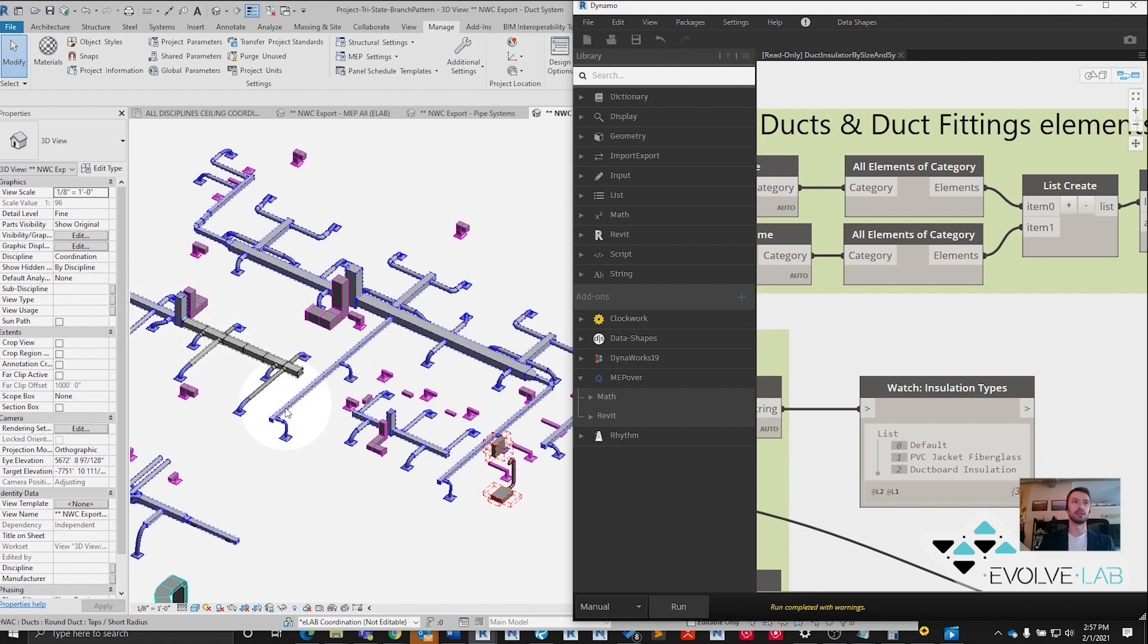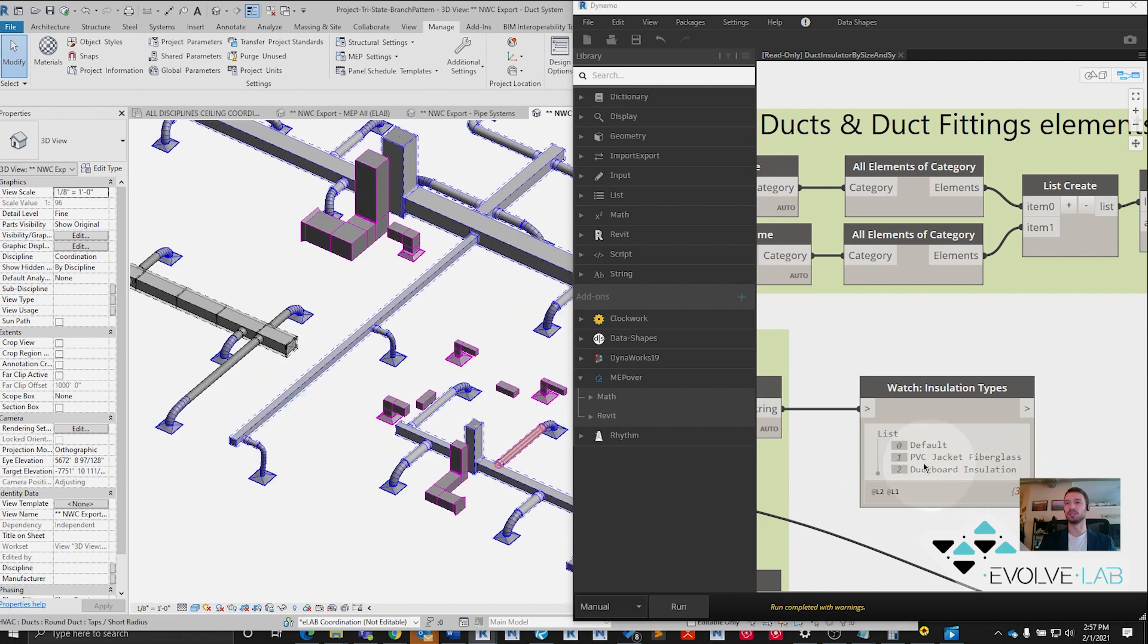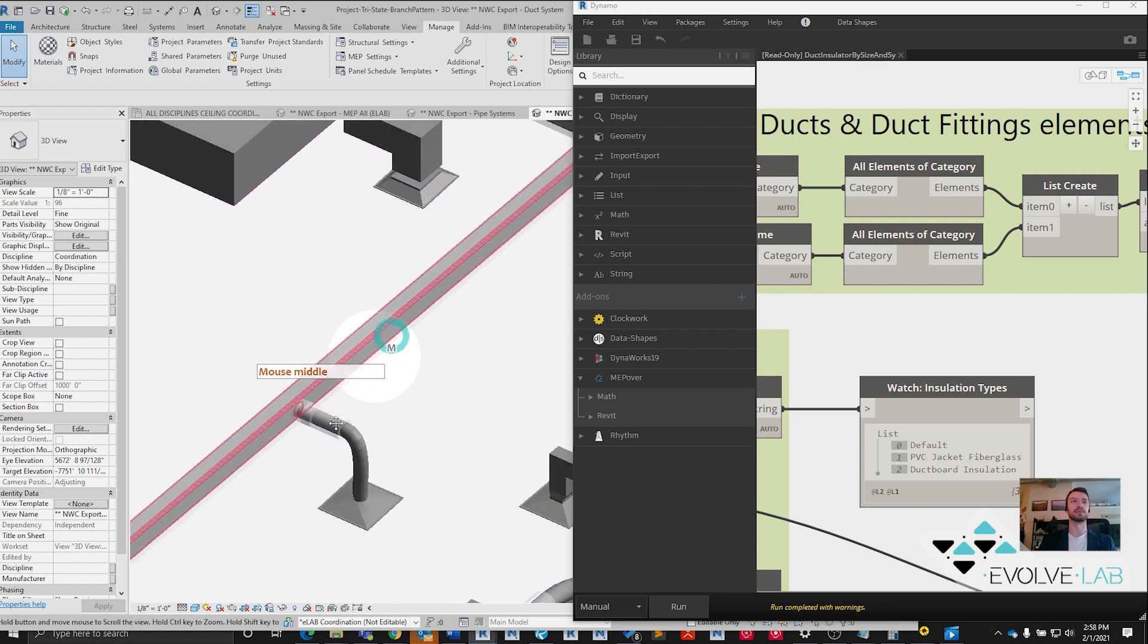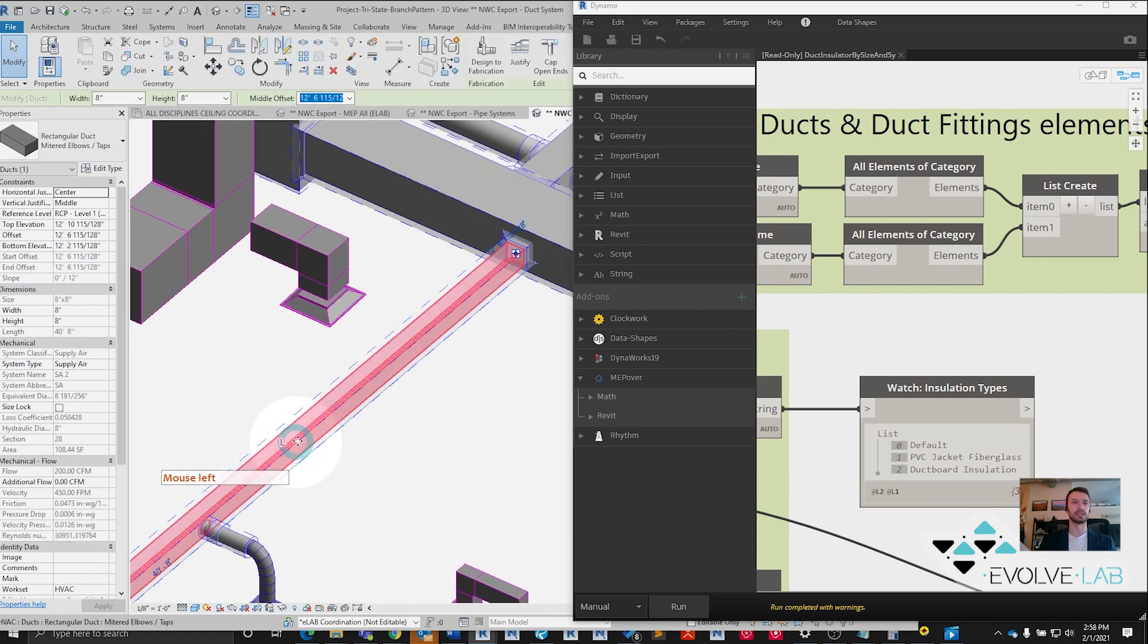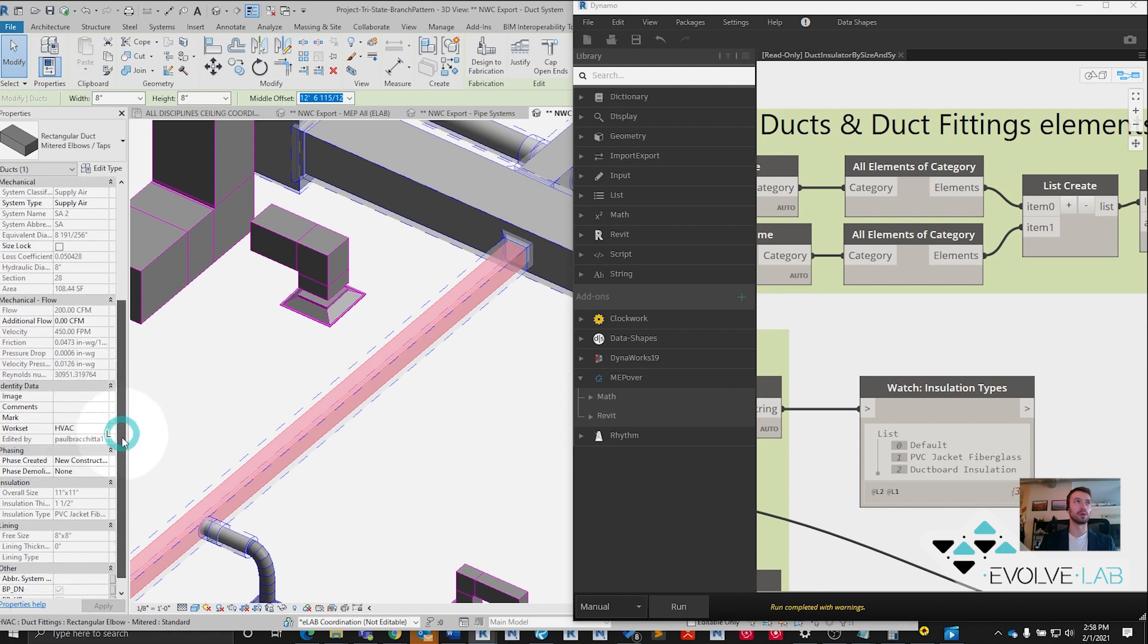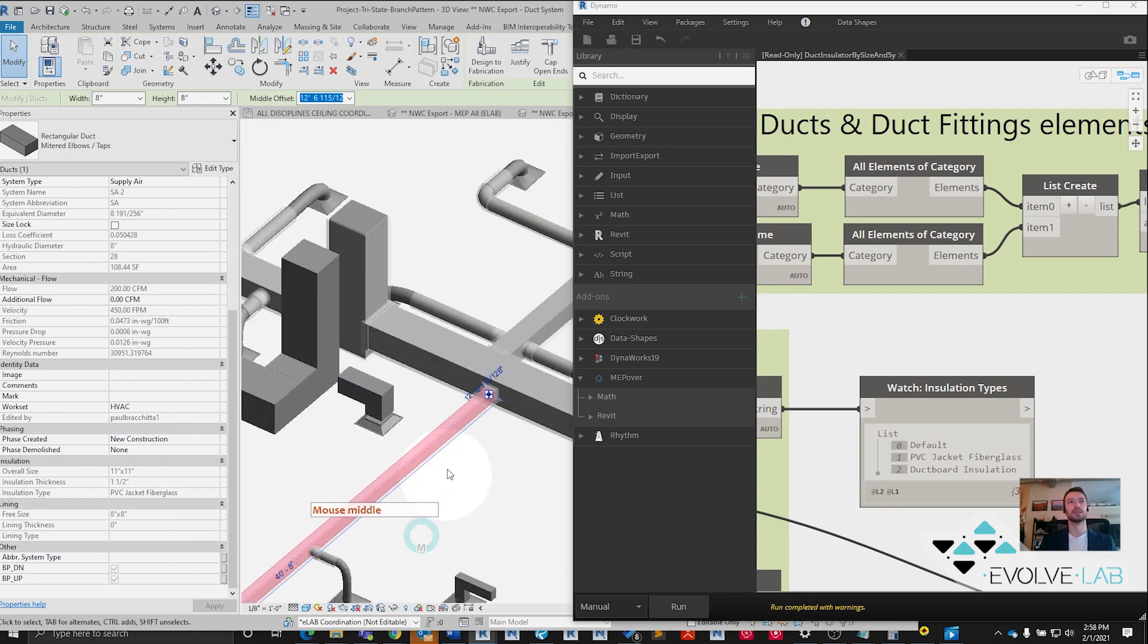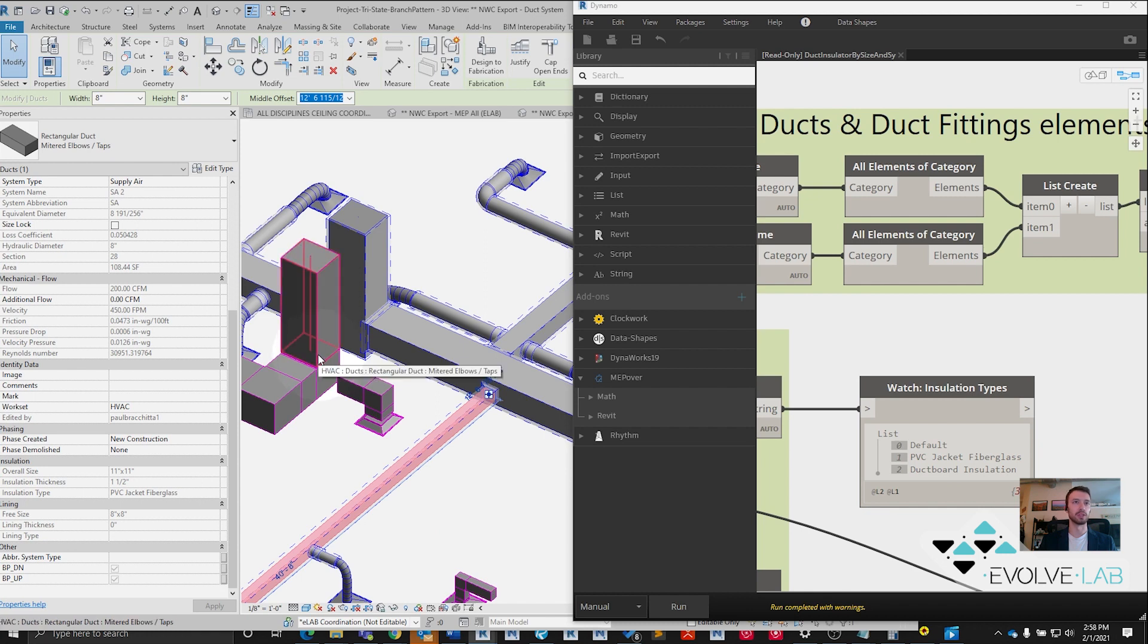You see every piece of supply air duct and duct fittings now has insulation on it, and it should be this PVC jacket at an inch and a half. Let's select on our piece of duct here. Scroll down in the properties palette to insulation: inch and a half PVC jacket. Excellent. None of the other systems, the return air here, that did not get insulation. That's exactly as we wanted.